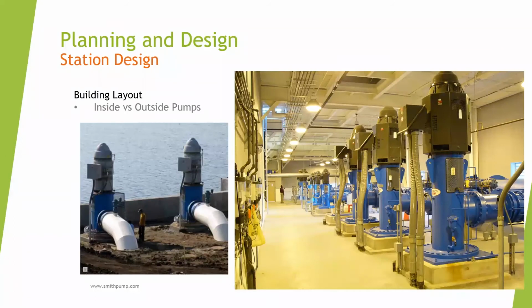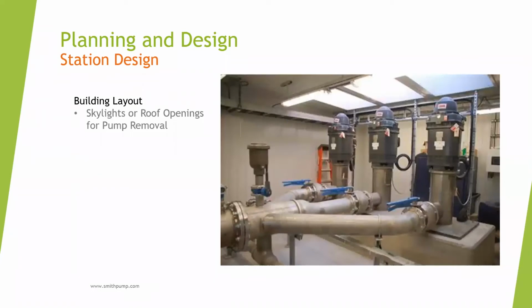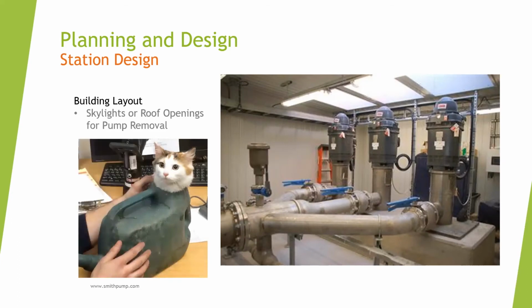So back to pump station design. Does the application or owner want equipment indoors or outdoors? Luckily, pumps can go in either. The type of motor enclosure is the only change between the two. If inside, remember to include an opening for future removal. Don't encase a building around the pumps and trap them like this cat. We've removed pumps stuck inside buildings, but it's much slower as equipment is disassembled piece by piece. Typically, an external crane will do the heavy lifting of installation and removal through a roof hatch.